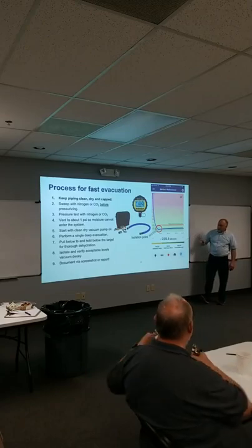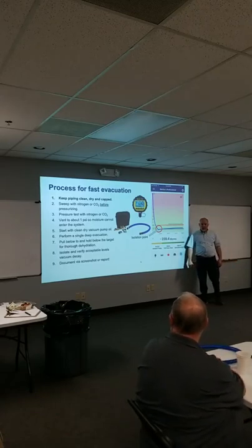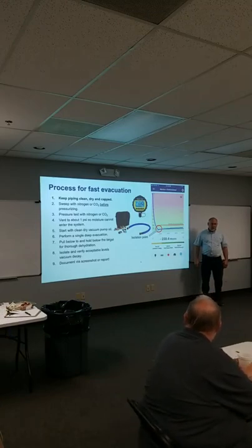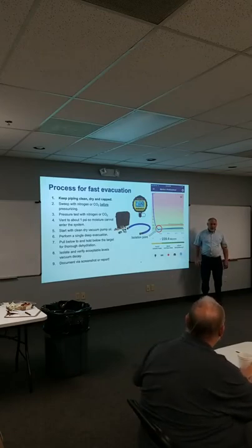The first time I tried this hose out, I went out and met Mark Jackson's company, Jackson Comfort Systems, on a job. We had 100 foot of 3/4 and 3/8 on a 4-ton coil, existing line set. They did an R11 flush on it, purged it with nitrogen. It was dry when I got there.